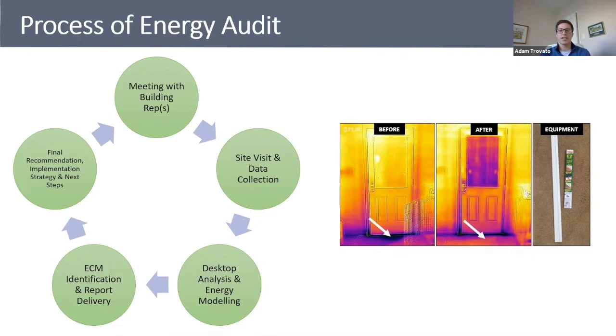Once that's complete, the auditor goes through the building envelope, mechanical equipment, and electrical equipment with a thermal imaging camera to do a thermal imaging test, which identifies areas of heat loss and poor thermal performance. Generally around the site visit, the building representative will collect data, including utility bills, building drawings, building condition assessment reports, capital plans, and so forth, to support the analysis.